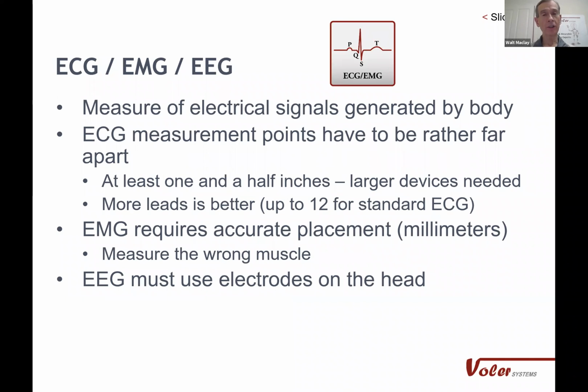Now, ECG, EMG, and EEG, it's all measuring electrical signals generated by the body. ECG, the measuring of the heart. Now, the standard is 12 leads. If you go to a lab or a hospital, you have a healthcare professional make an ECG measurement, they're going to use a 12-lead ECG. There are devices now with just 2 leads that give results almost as good as the laboratory devices. But you've got to be careful that they're spaced far enough apart. And I'm saying here 1.5 inches, that's when it's on the chest. If you place it elsewhere, it gets to the point where you can't make a measurement. So as on the wrist, for example.